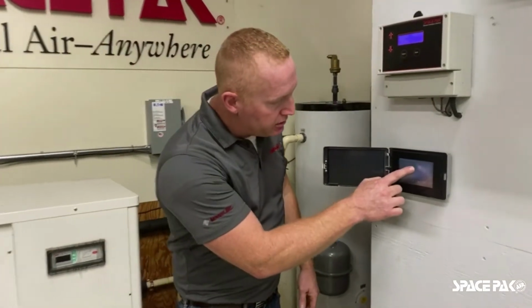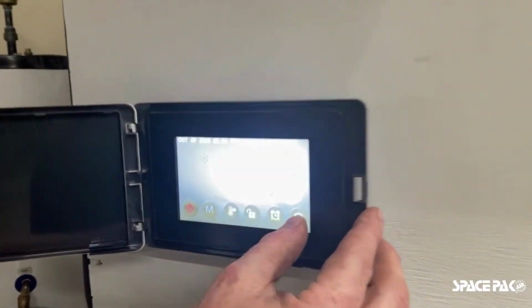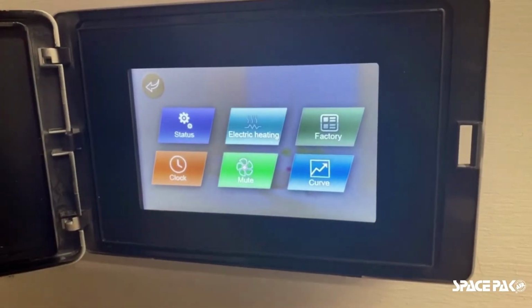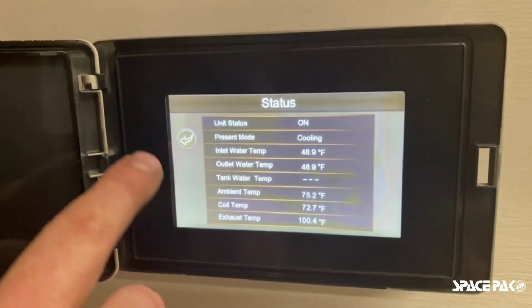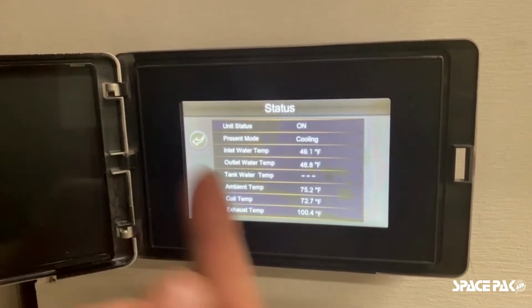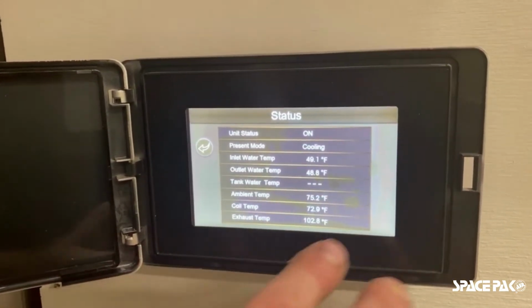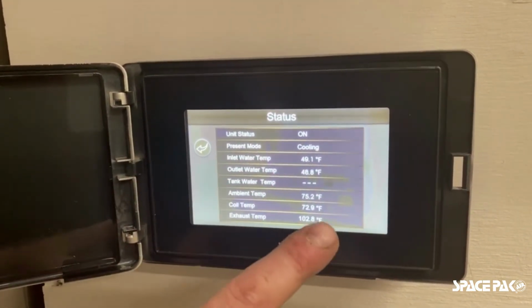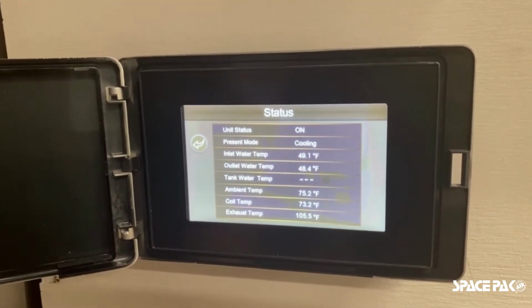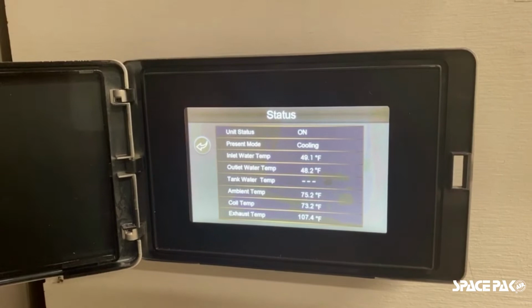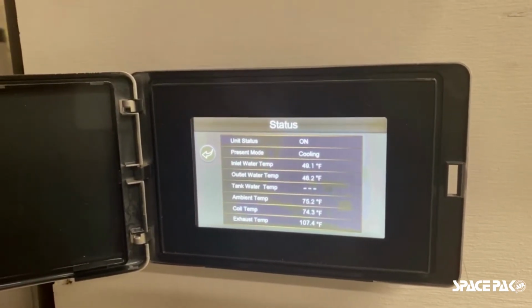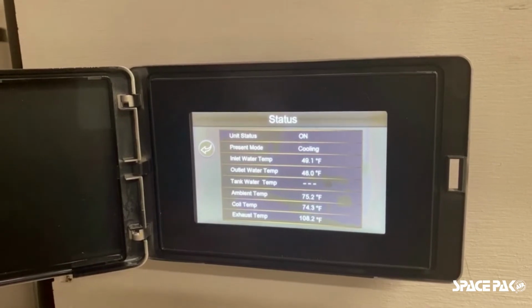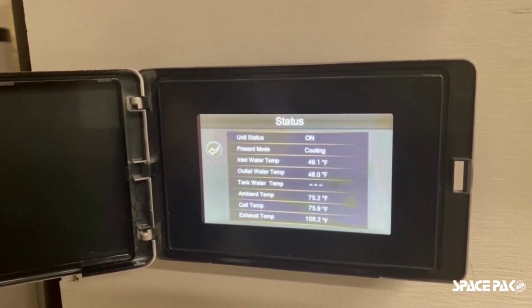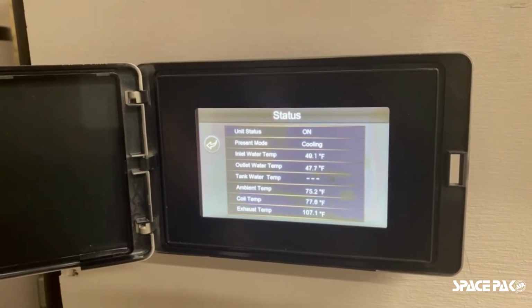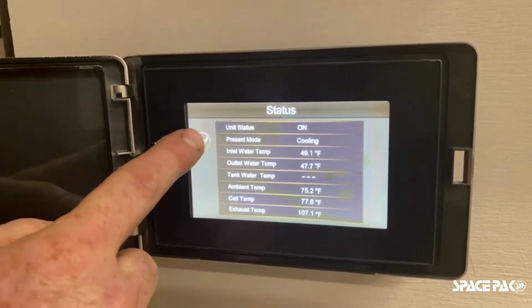Now, one of the things to make sure of, when we go to settings, okay, we're going to click on settings. Under very initial start, we're going to go to status here. It's going to kind of give us an overview. Unit status is on, cooling mode on. It's also going to give us a quick rundown of our inlet and outlet water temperatures. So we're bringing in 49.1 degree water, and we're outletting 48 degree water. So right now we have a 1 degree delta T, which may not seem like much, but being an inverter driven unit, we actually start slow with the inverter frequency, right? So low speed, and then we slowly ramp up to high speed.